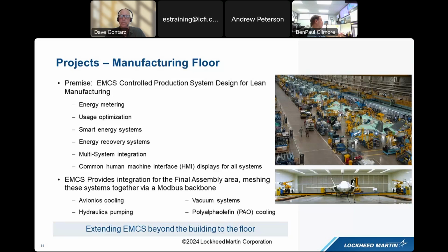There are humidity modes, painting modes, sanding modes, and they tend to come up with modes that we have to develop for them. We put in a touch screen we can reprogram for them to select their modes. They press one button, and $20 million worth of mechanical hardware activates and does whatever is required to get that bay into the correct operating mode to paint an F-35.